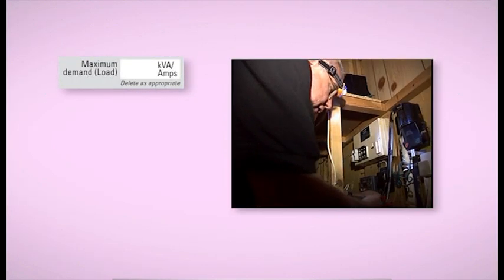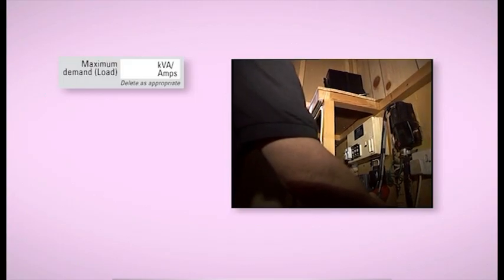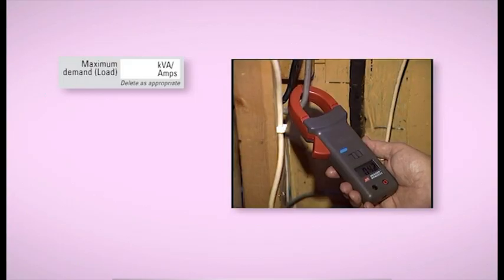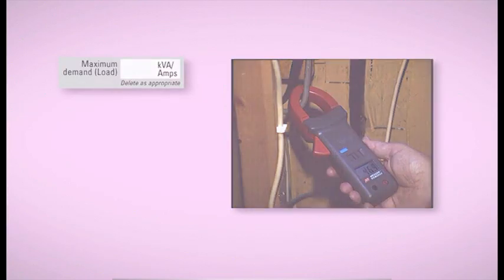We're going to finish today by looking at information particular to the electrical installation certificate. One box we didn't discuss is maximum demand, which is under particulars of the installation at the origin. Normally, this figure would be the maximum demand taking into account diversity calculated by the installation designer. However, for work which is adding additional circuits and loading, it may be necessary to determine the existing maximum demand before commencing with the work, so that it can be ascertained that the wiring and the equipment installed, especially at the origin, is suitable for the additional load.